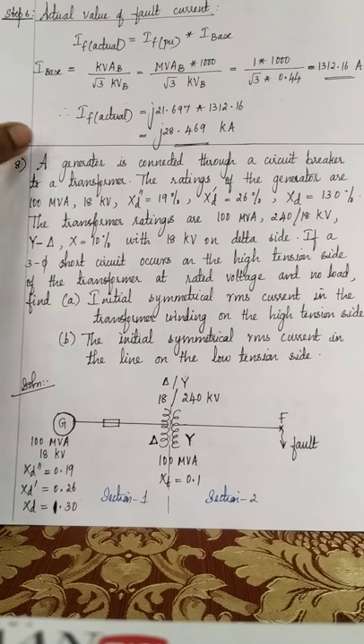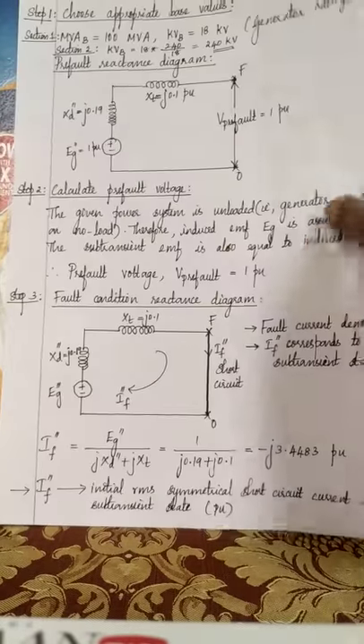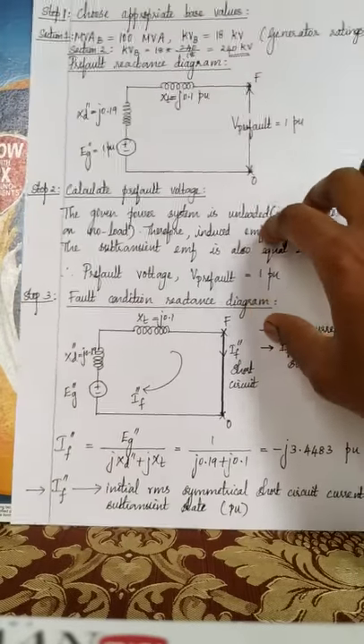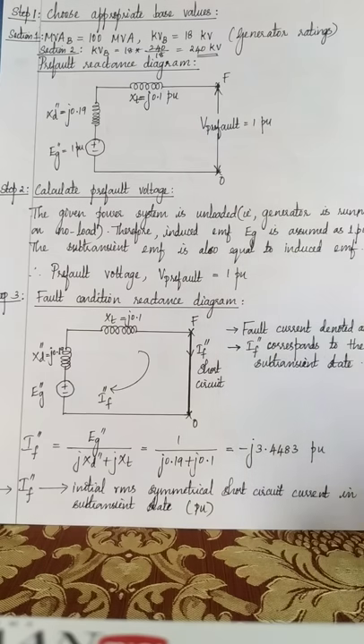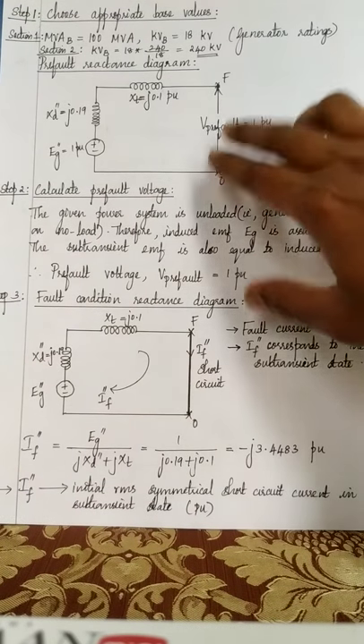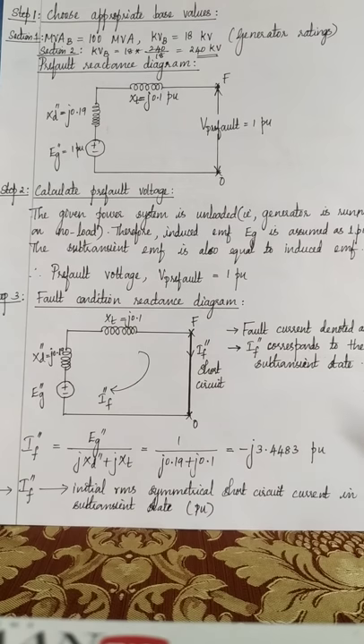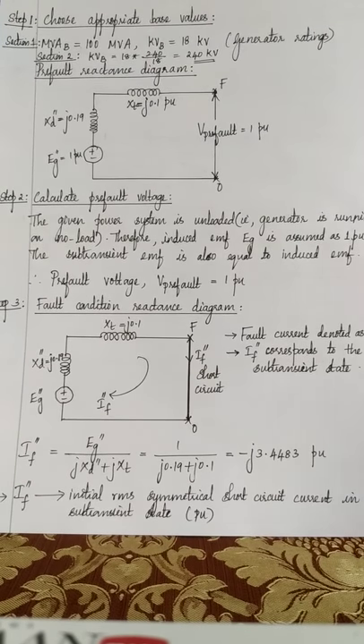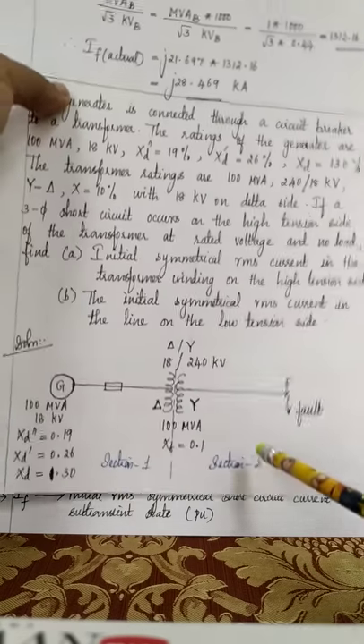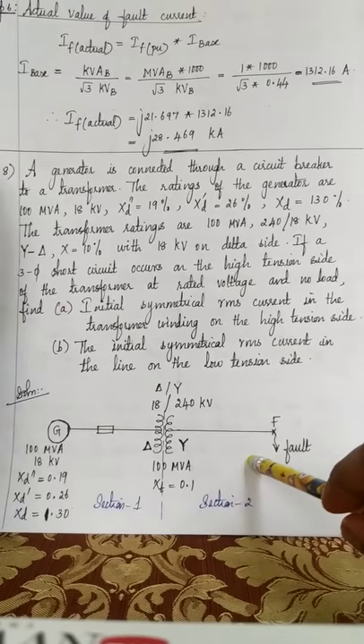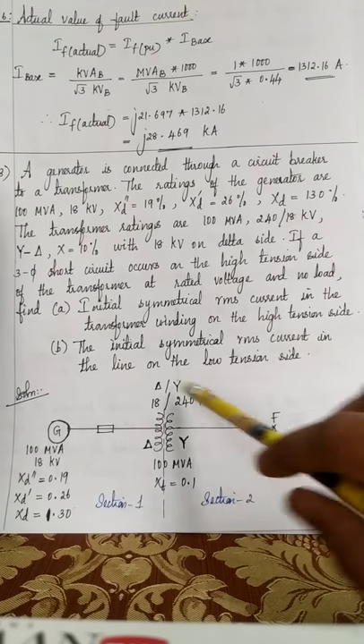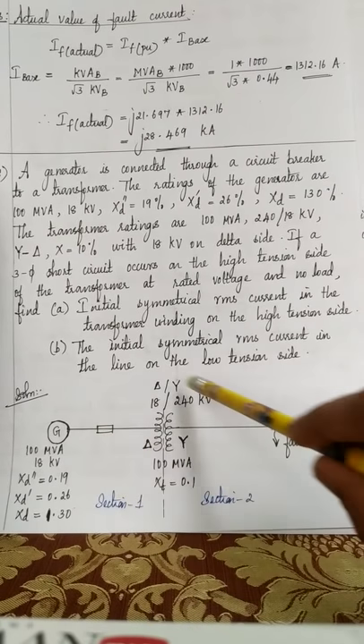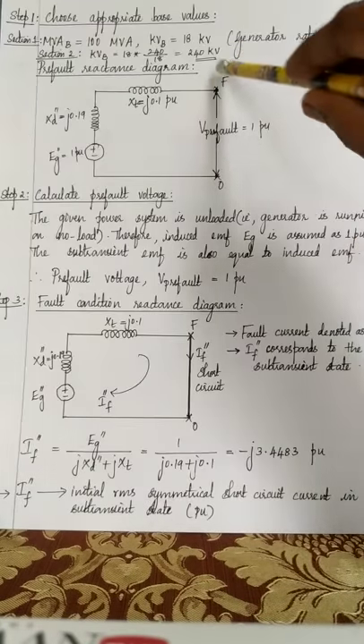Okay. So now what is step 1? You have to choose an appropriate base value. So we are taking section 1 ratings, that is the generator ratings, as the common base. What is MVAB? 100. What is KVB? 18 kilovolt for the generator side. Then using the transformation ratio of this transformer, we find the KVB in section 2. What is KVB in section 2? Section 1 KVB 18 into 240 by 18, which is 240 kilovolt.